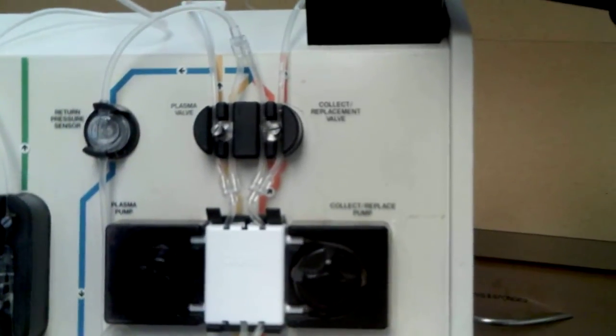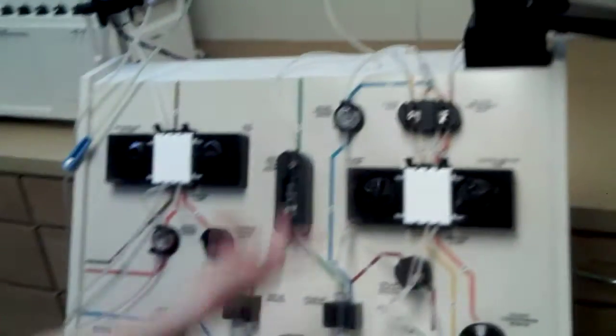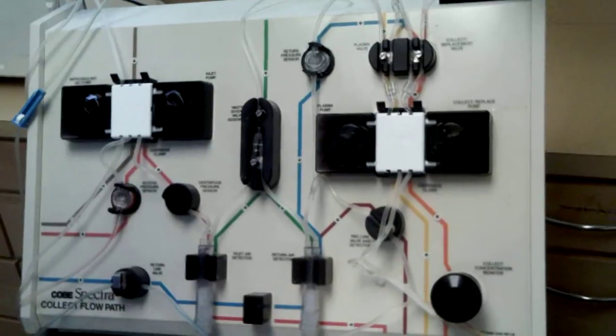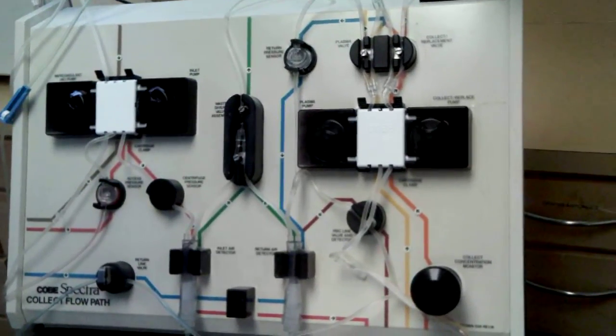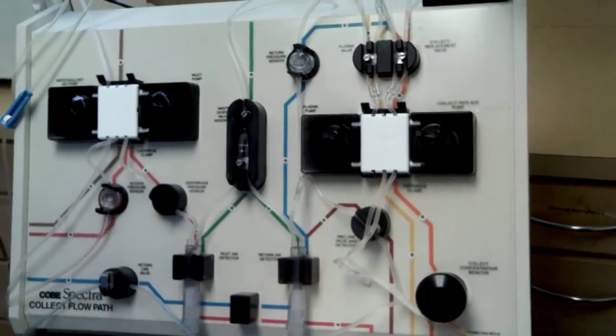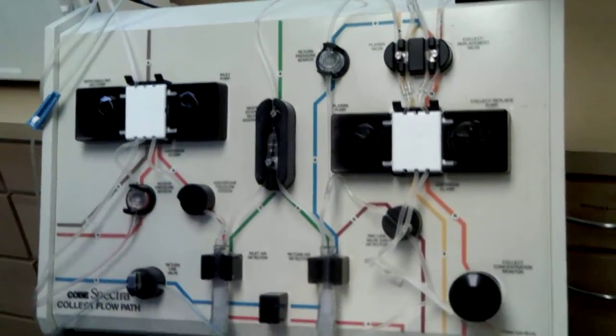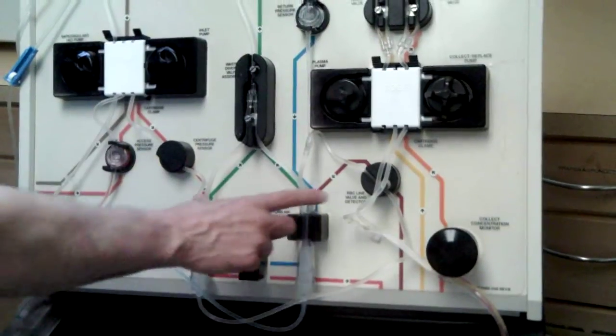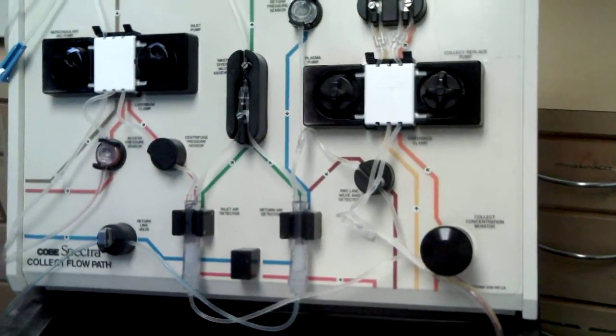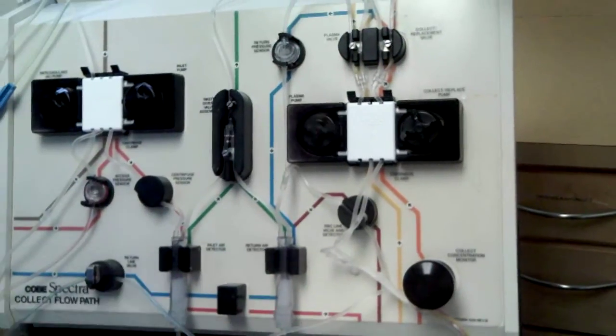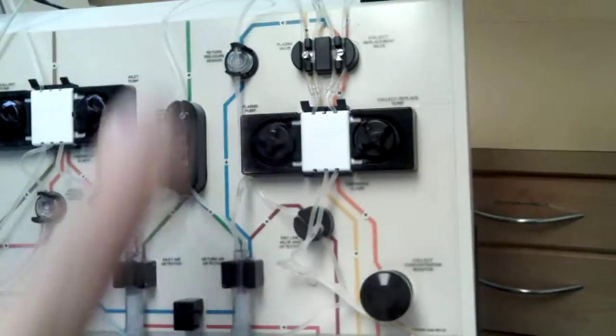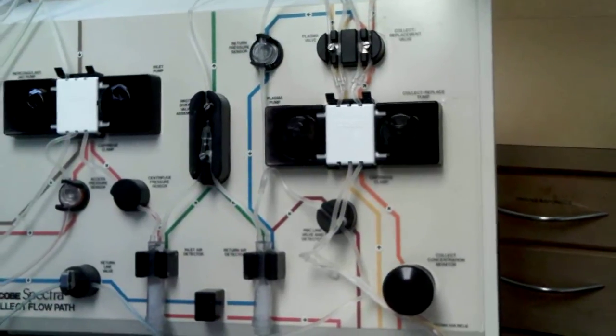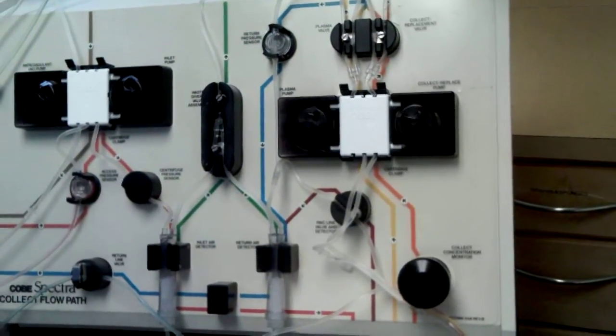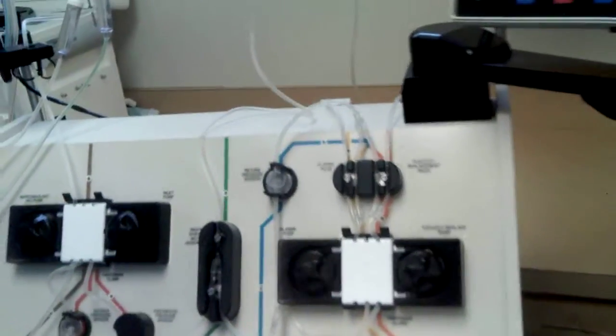This is still priming the centrifuge channel, it says. Yeah. Okay. It filled fluid into the channel and is sucking it back up through the line. I'm just going to try and clear all the air, right? Eventually it will clear the air out of the chambers, although a little bit of air can sometimes remain. And it will also clear the air out of all the centrifuge channel, which is what's happening now. You can see it's sucking out through the centrifuge channel. There's some air zipping along there, we can see.